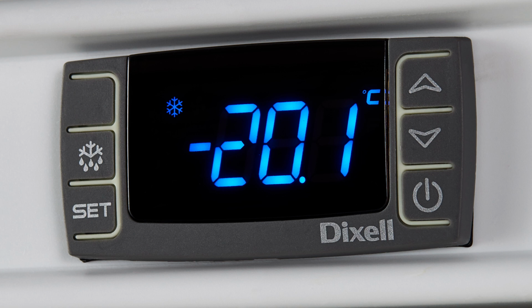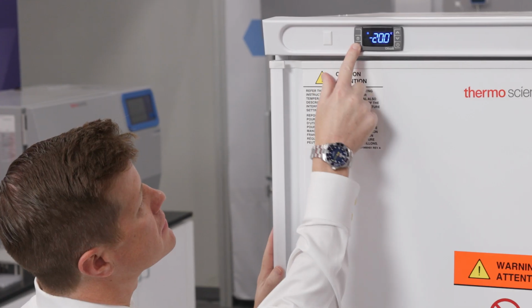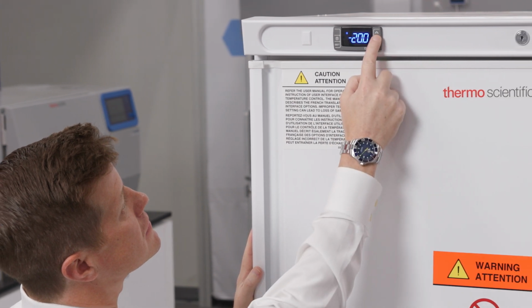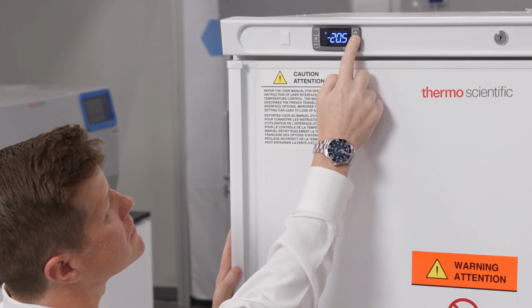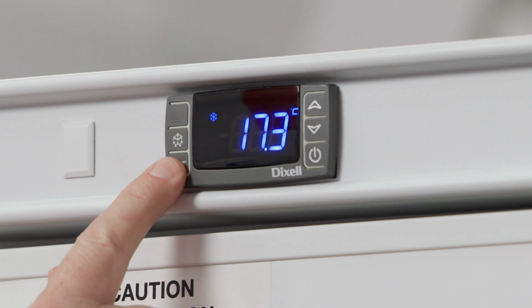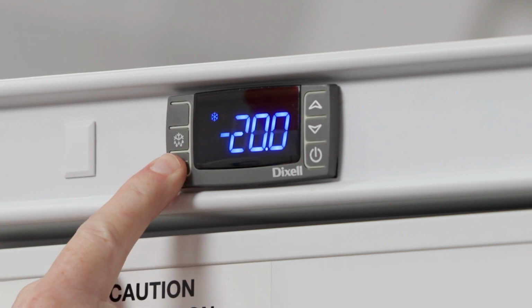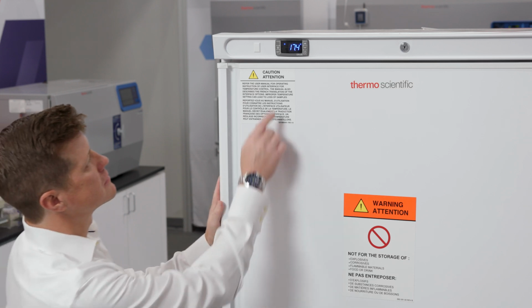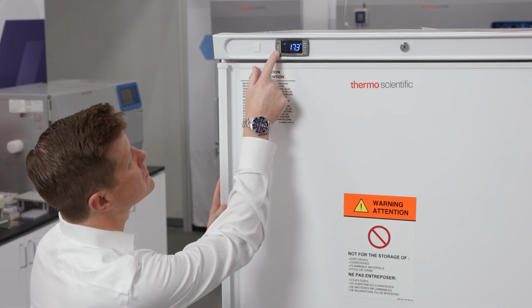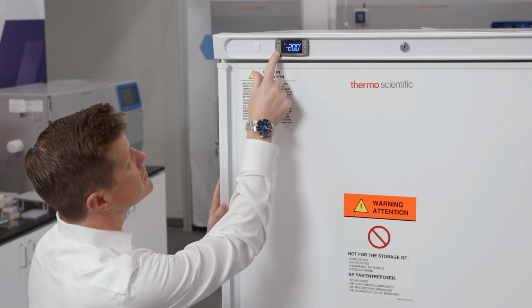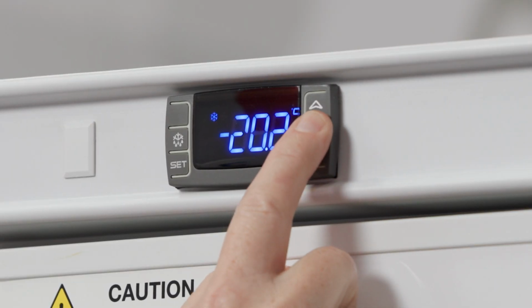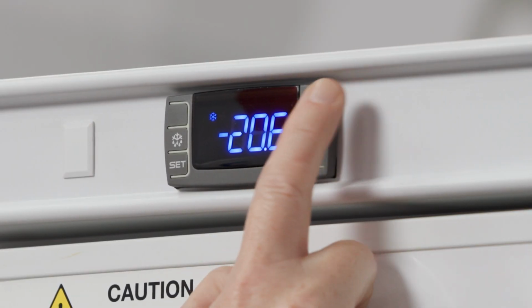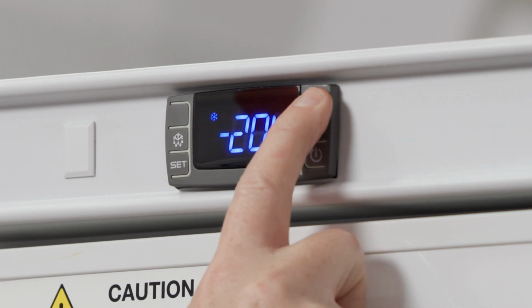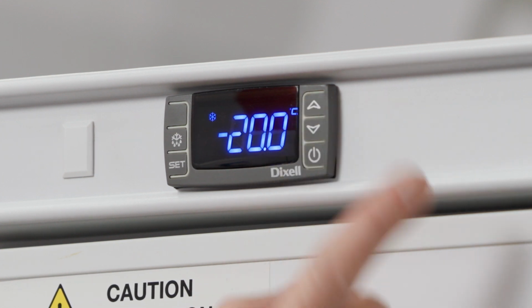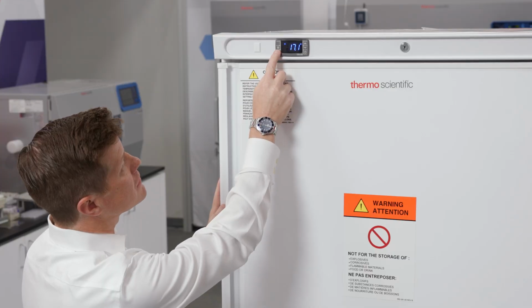The unit will come set at a factory temperature set point of minus 20 Celsius degrees. If you would like to program it to an alternative set point, follow these four steps. 1. Push the set key for more than 2 seconds to change the set point value. 2. The value of the set point will be displayed and the snowflake icon on the LED screen will start blinking. 3. To change the set value, push the up or down arrows within 10 seconds. 4. To save the new set point value, push the set key again and wait for 10 seconds.